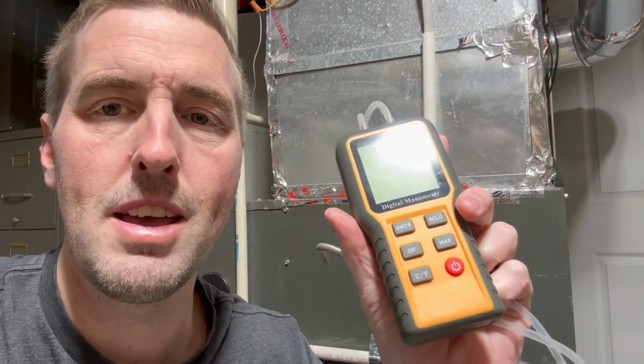So what we're trying to do is just isolate the impact of the filter by doing a comparison between each of the measurements. Probably the single most important tool that we're going to be using today is the manometer. This is going to allow us to measure static pressure inside of our furnace. This is a very handy tool anytime you're trying to diagnose furnace issues or furnace performance. You can take measurements at various points throughout the furnace. So what we're going to be using this for today is really measuring the inlet to the blower. So it's downstream of the filter, upstream of the blower. And this, again, going back to that milkshake analogy, is going to give us an indication of how much restriction there is when the blower is trying to move air through the system. And a lot of that depends on the upstream components, including the filter.